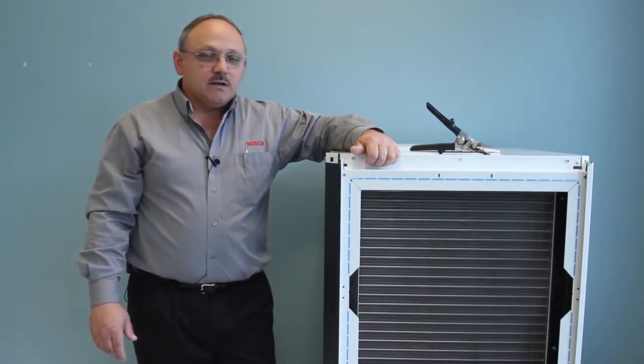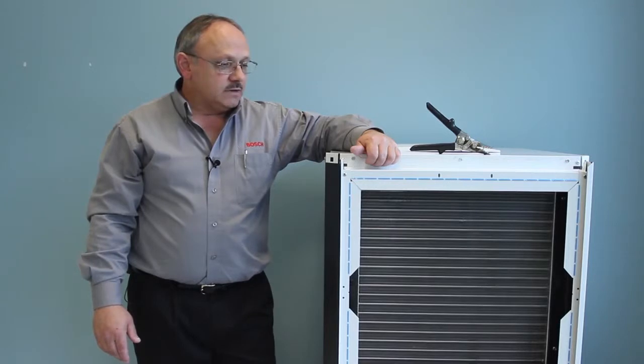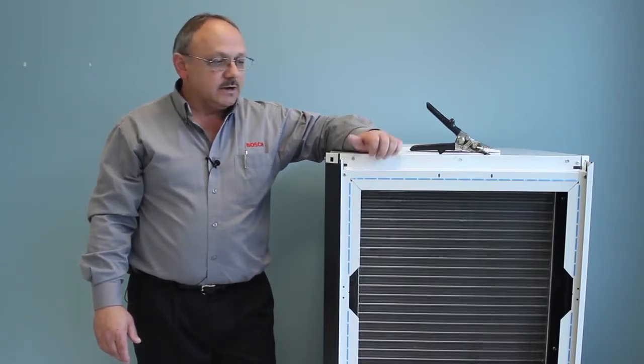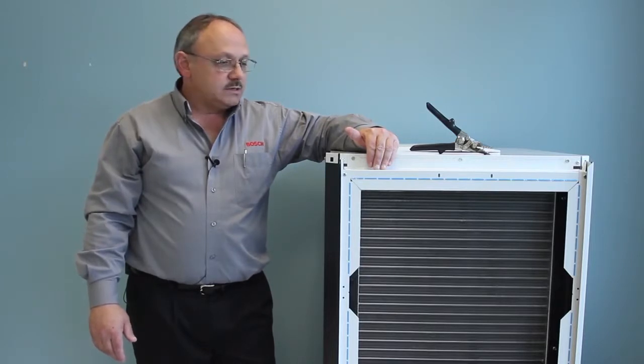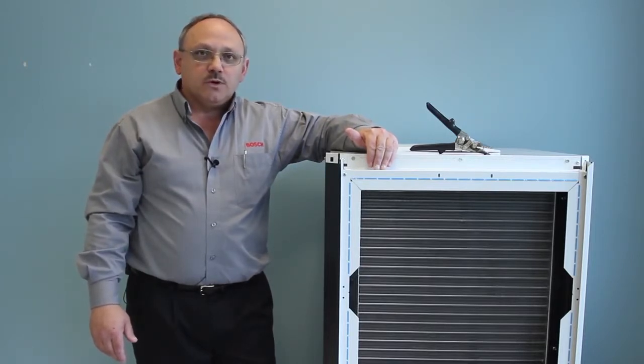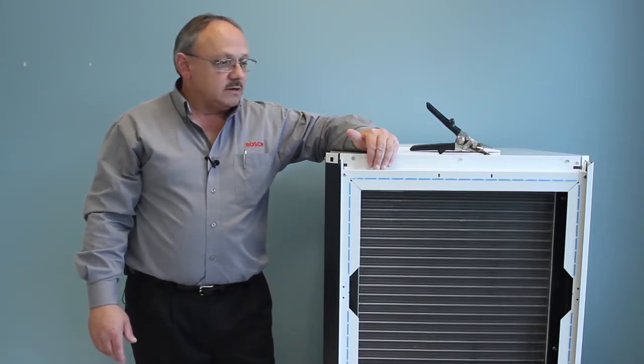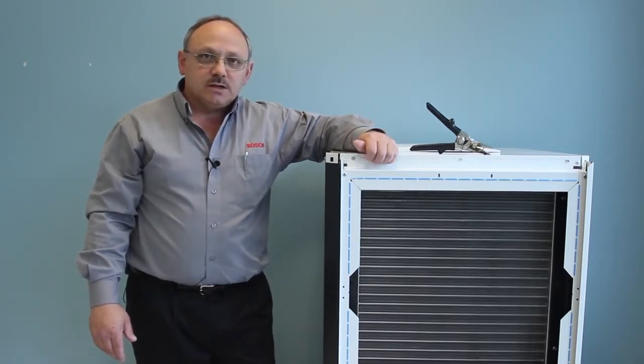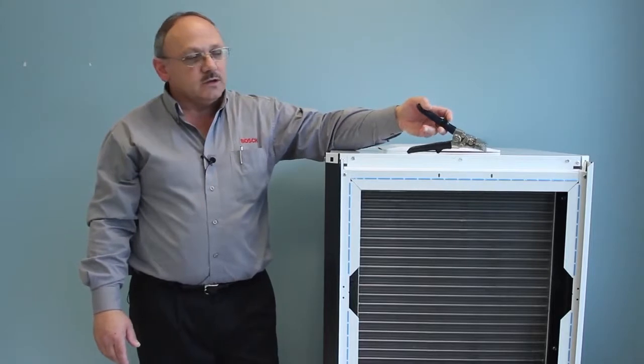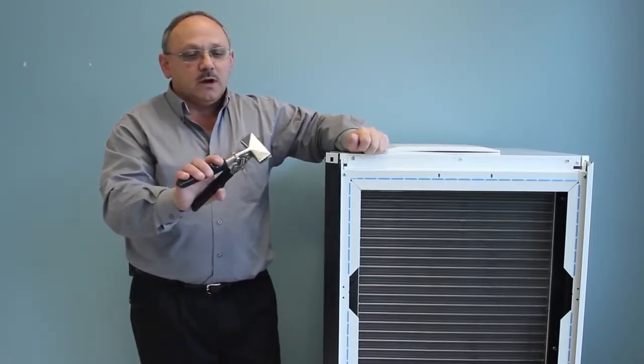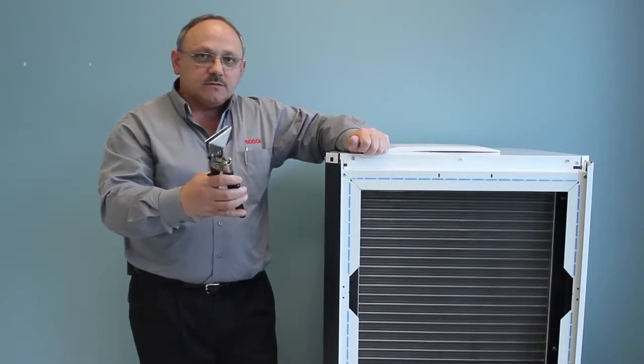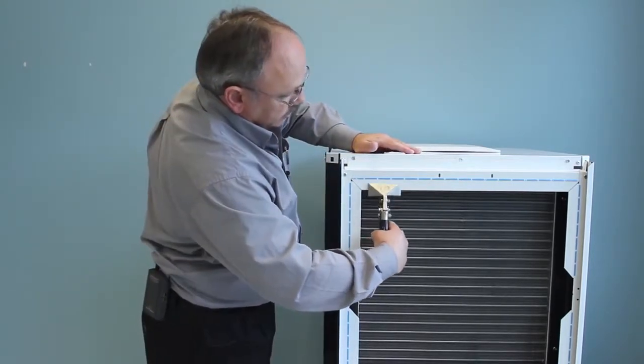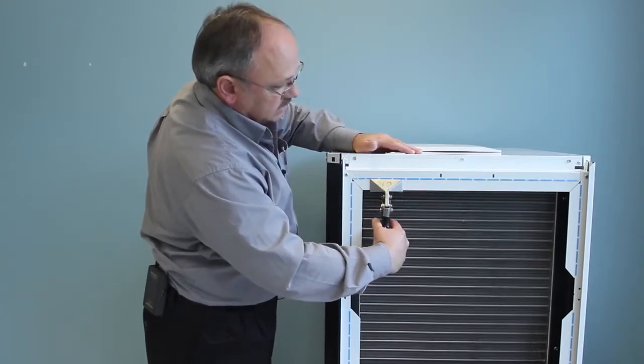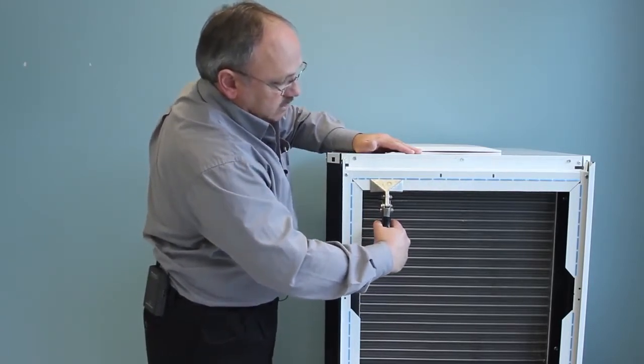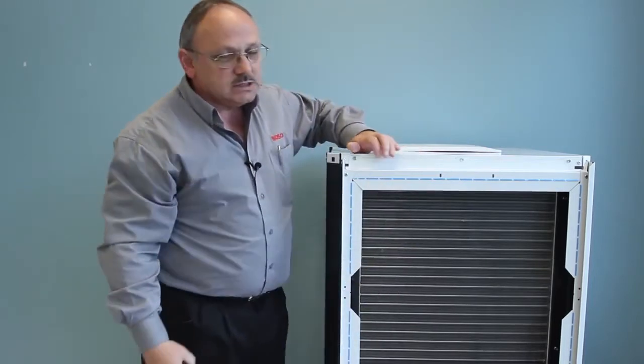So make sure you consult the installation and maintenance manual and follow the steps that fit your application. Once everything's complete and all the panels are back on, and you've installed your corner caps, the return air filter grill and filter rack in place, there's one more thing you might want to do before you set the equipment in the mechanical room or where you're going to install it. There are duct flanges that are shipped in the folded down position, and they're manufactured what we call origami style, where you can simply take a hand seamer or a good pair of lineman pliers and bend those duct flanges into place. You just put your hand seamers up against the perforated section of the duct flange and bend it into place all the way around before you set it into place and make your duct connections.